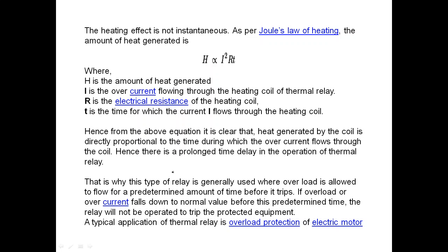Hence, there is a prolonged time delay in the operation of the thermal relay. That is why this type of relay is generally used where overload is allowed to flow for a predetermined amount of time before it trips. If the overload or overcurrent falls down to normal values before this predetermined time, the relay will not operate to trip the protected equipment. A typical application of the thermal protection relay is overload protection of an electric motor.